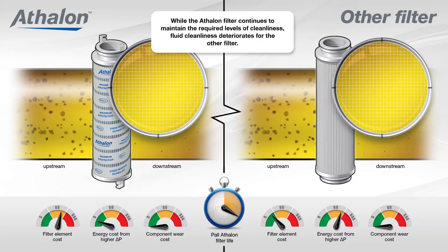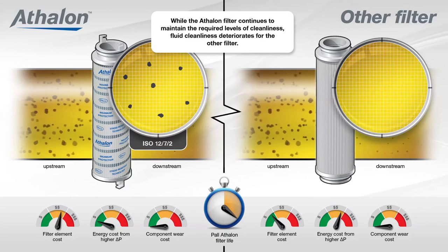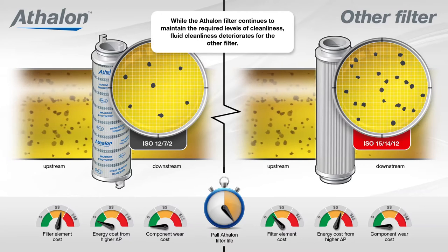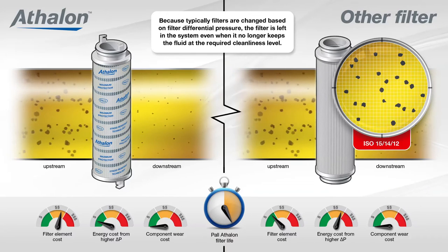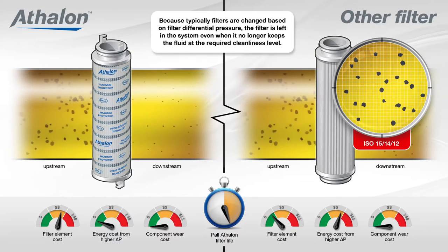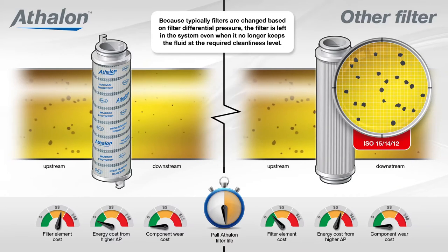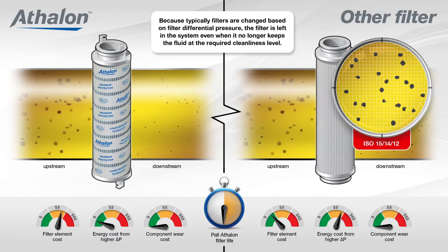While the Athalon filter continues to maintain the required levels of cleanliness, fluid cleanliness deteriorates for the other filter.